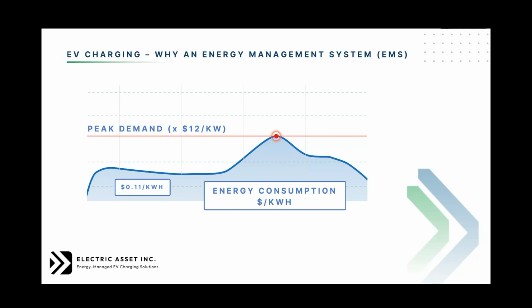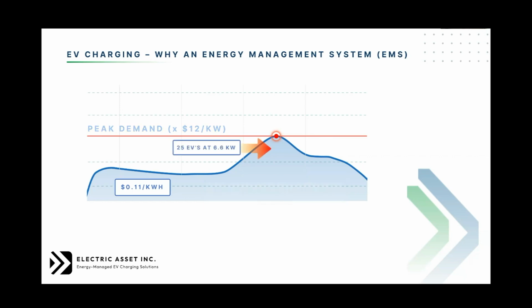And you get billed $12 a kilowatt. This is a key point, because the blue area, cars do not take that much energy to charge, and it doesn't cost that much money, but its impact on peak demand can be huge. So if we take a scenario where 25 electric vehicles all come home around in, say, a 2 hour stretch, some of them need to charge for 20 minutes, some need a couple hours. But regardless, for 20 or 30 minutes, all 25 are charging at the same time, each plugged in. It's not looking at other EVs or what else is going on in the building; it's going to take whatever energy is available to it.